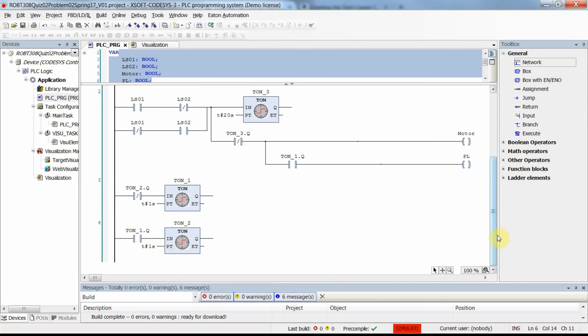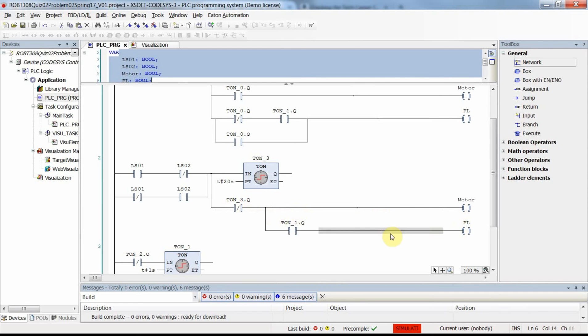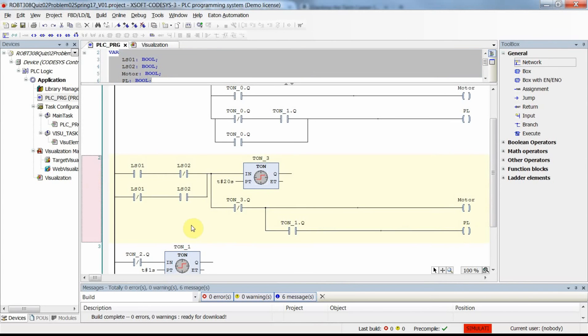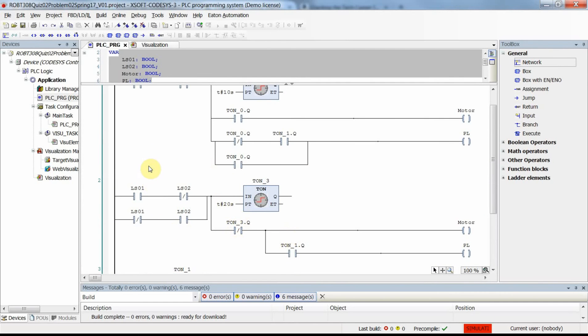For the flashing behavior, timer TON_1 and TON_2 are interlocked — the output of the first timer feeds into the second, and the second feeds back into the first with negation, creating a flash oscillation. For the second scenario — one switch closed, one open — we check that condition and run the motor for 20 seconds (instead of 3 minutes), with the pilot lamp flashing during those 20 seconds, then both turn off.